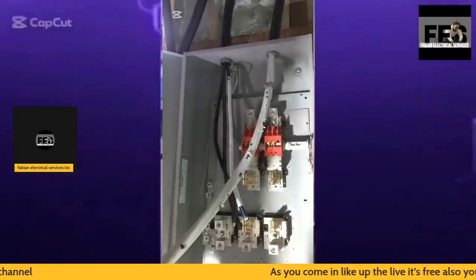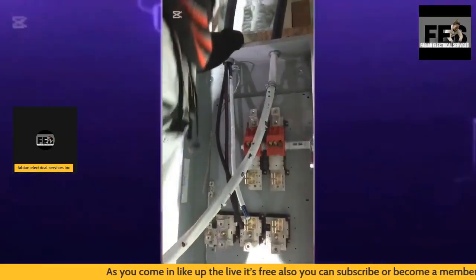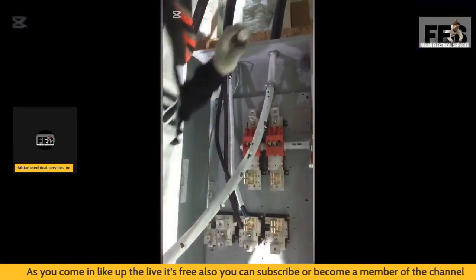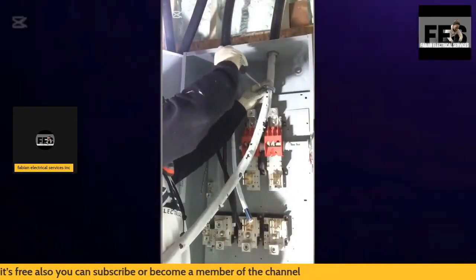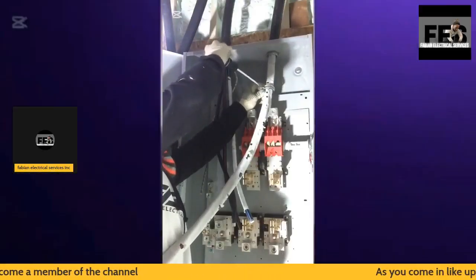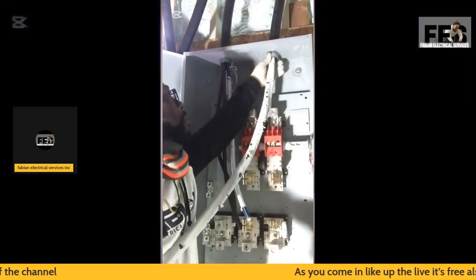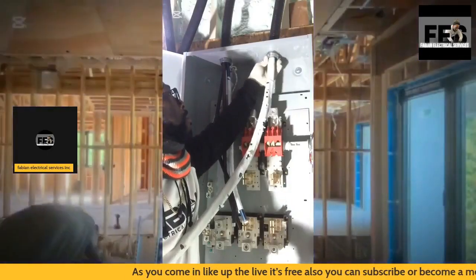As you can see on the left hand side, you're going to see the other installation. You're going to see my wire is grounded off onto the ground bushing. It is in code compliance. It is a code rule that states that. It is inside of the electrical code book where you would find it. You just have to search.